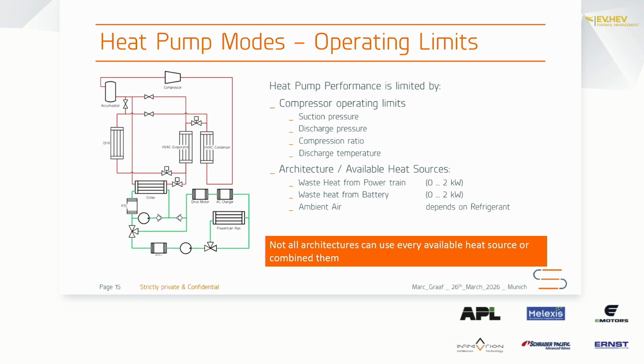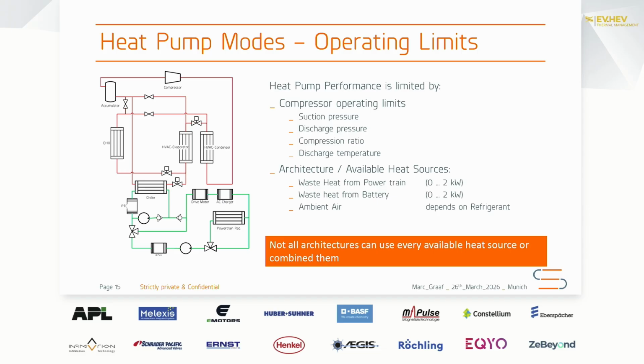normally automotive compressors are not hermetic, so you're not allowed to go below 1 bar absolute pressure, to prevent air from permeating into the refrigerant system, and with air also humidity, and this could then lead to damage to the compressor over time or reduce the durability of the compressor. There's a discharge pressure limit that depends on the refrigerant that you're using. So in the benchmark there is a CO2 system, which has, of course, higher suction pressure and discharge pressure limits.